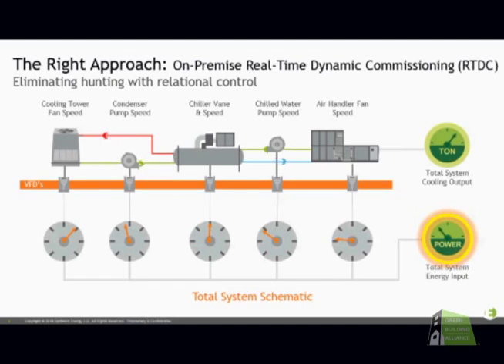So one thing I should mention that we're assuming is that all of your equipment is going to be variable speed. Typically on new plants, that is the design. It's pretty well accepted now to have variable speed drives on just about all motors. The only exception that I might still see on newer plants is condenser water pumps, although people are beginning to understand the need for that. And one of the things I'll say on the condenser water side, if you're going to just have an arbitrary set point for that condenser water pump, you might be running it more than you need to at all times, even if you already have a variable speed drive on it.